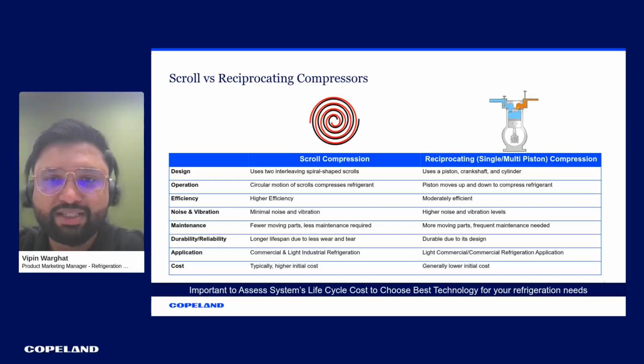So if you compare this technology from design point of view, scroll has one stationary spiral, and the other is moving around it, while the reciprocating is piston, crankshaft and cylinder based components which ultimately are used in the compression. And operation is, for scroll, one of the scrolls is stationary, and the other is moving scroll, which is creating that compression in the compression chamber, while reciprocating is up and down movement of the piston which is connected to the shaft.